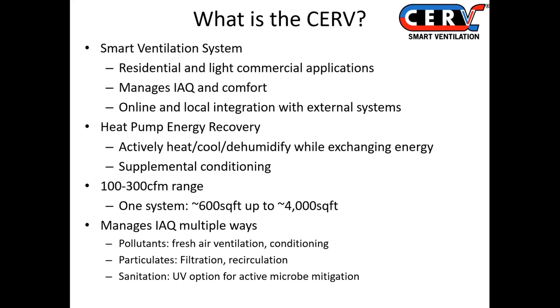So what is the CERV exactly? It's a smart ventilation system geared towards the residential and light commercial applications. It manages air quality and comfort in a home or commercial application. It has online and local integration with external systems. The energy recovery is done through a small heat pump system. So it's a heat pump based energy recovery, as opposed to conventional ERVs and HRVs with the heat exchange core. That allows for supplemental conditioning from the system. So we can use that same small heat pump to add heating or cooling dehumidification to the space.